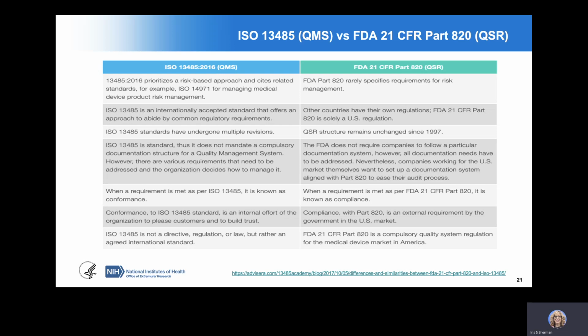You will hear ISO 13485. These are the international standards for quality management. And this chart does a nice job of comparing the two. But remember, your quality management requirements is a US requirement. And the design controls, the quality practices, and the procedures incorporated into design and development applies to both systems, though. And the FDA is currently working to align these two practices. These apply to all Class 2 and Class 3 medical devices, certain Class 1 medical devices, to include software medical devices.